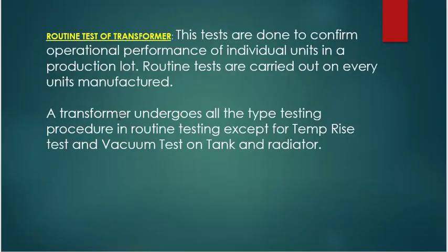The routine tests of a transformer are done to confirm the operational performance of individual units in a production lot. Routine tests are carried out on each and every unit manufactured. A transformer undergoes all the type testing procedures in the case of routine testing also, except for the temperature rise test and vacuum testing on tank and radiator.